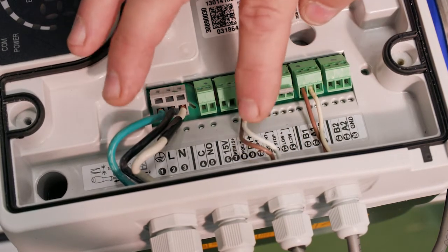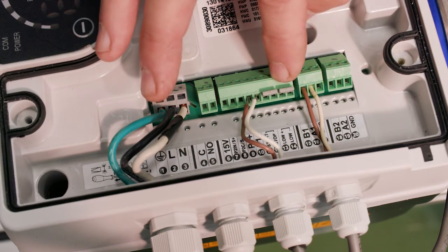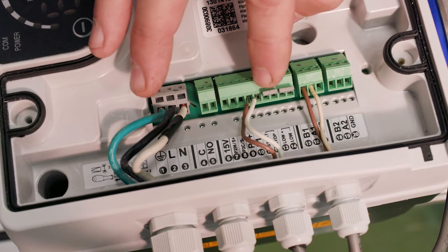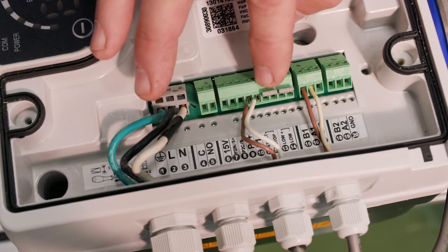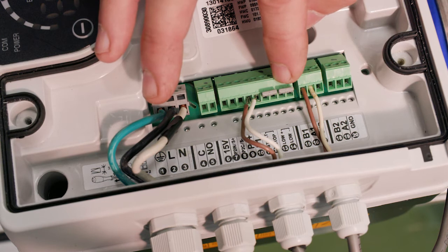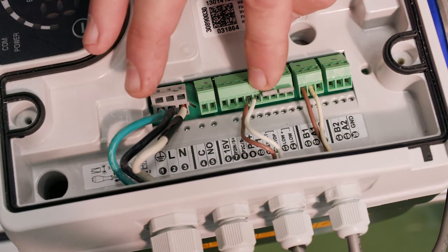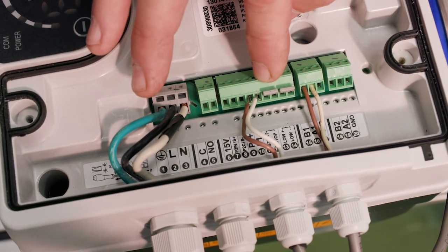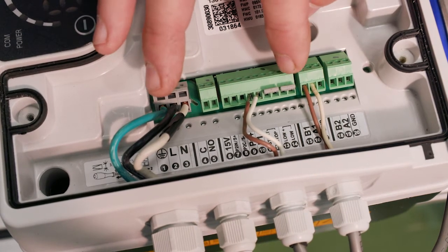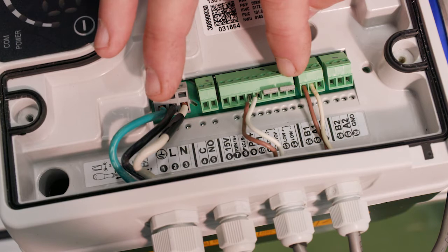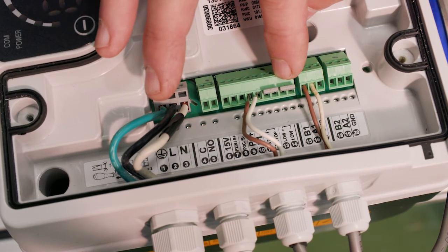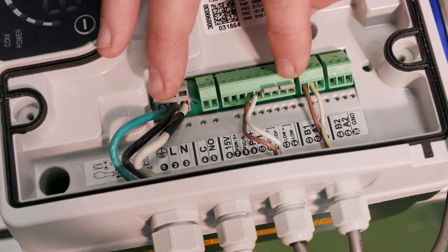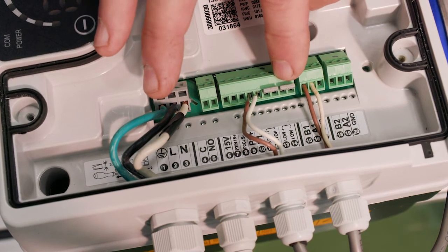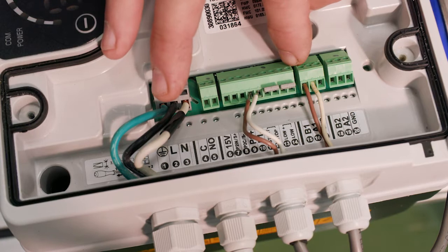Moving on to the next 2 terminals, we see 11 and 12 and 13 and 14. These are normally closed, and we can see that they come with a jumper. Closed means run, and if it was open, it would turn the drive off. The first terminal is just a start-stop, so if you want to control this with some other switch, simply closed means run, open means off. The extra set of terminals, 13 and 14, are designed for a type of low water switch. Again, normally closed. When it's tripped, it's open, and it would turn the drive off. In this case, we're not using any of these switches, so we're going to leave the jumpers in there.